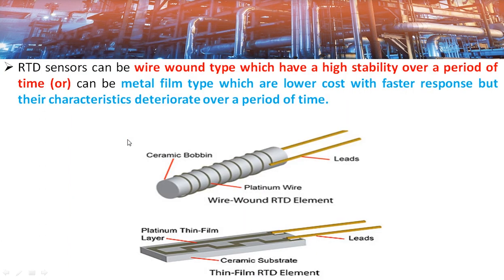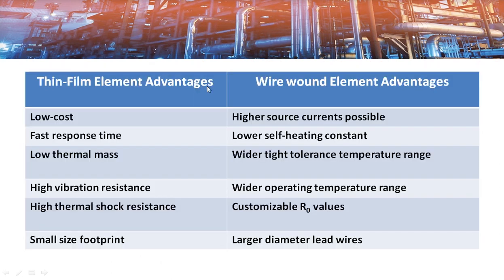We have seen the classification of RTDs based on material of construction. Now, looking at RTD sensor classification based on construction, they are classified as wire wound type and thin film type. Wire wound RTDs are used in applications requiring high stability and low self-heating effect, whereas thin film RTDs are used in applications requiring faster response and low cost. The table shown here summarizes the advantages of each type.